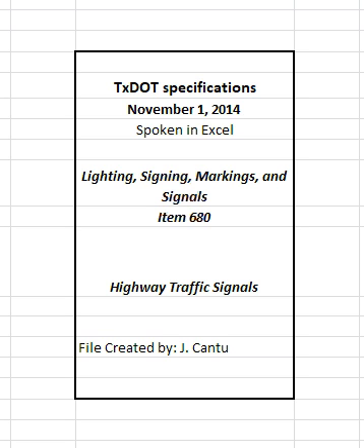3.1.1.4 Grounding and bonding. Ground and bond conductors in accordance with the NEC. Ensure the resistance from the grounded point of any equipment to the nearest ground rod is less than 1 ohm. Install a continuous bare or green insulated copper wire, equipment ground, throughout the electrical system that is the same size as the neutral conductor, but a minimum number 8 AWG.